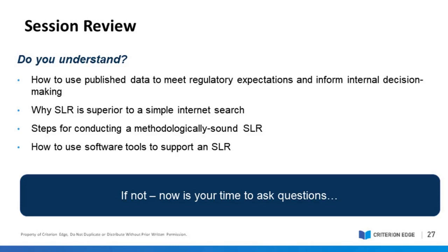Do you currently, yes, we do have a scoping document in which we establish the state-of-the-art strategy and how we'll go about finding state-of-the-art. And part of that, as I just described, is what the safety and performance endpoints are. What are we going to be looking at up front? I glossed over scoping as one of the steps, but to us, it's one of the most critical steps. It ensures that everybody's on the same page and we're moving forward in a focused manner on building a very complex document called a clinical evaluation report. So we most definitely do a lot of that work in the scoping.